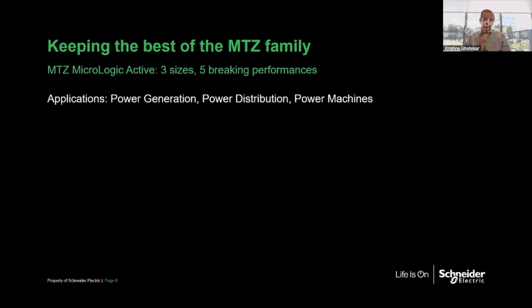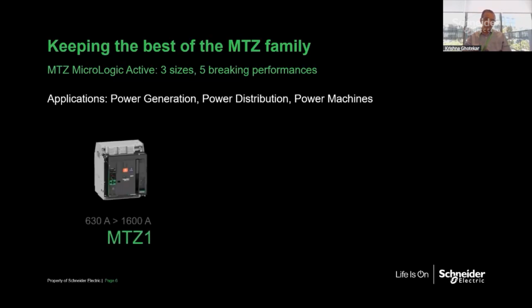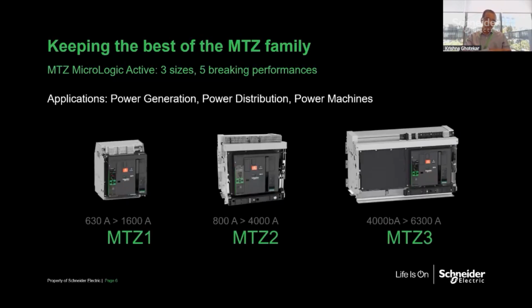So as I mentioned, since 2000, we tried to keep the same dimension of the product, so that whenever we upgrade or keep pace with digitization and the multiple innovations happening in the market, along with those innovations or new features added to the product, there is minimal or no impact on our panel builders, integrators or OEMs. So that's why the dimension of the product, the cutout, remains exactly the same for all the ranges. That means whether it's MasterPact NT and NW, if you have the standardized design with the cutout, everything, the same design of your panel fits exactly into MasterPact MTZ MicroLogic Active.